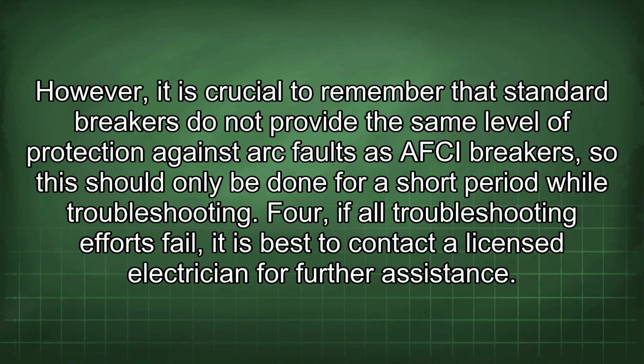However, it is crucial to remember that standard breakers do not provide the same level of protection against arc faults as AFCI breakers, so this should only be done for a short period while troubleshooting. 4. If all troubleshooting efforts fail, it is best to contact a licensed electrician for further assistance.